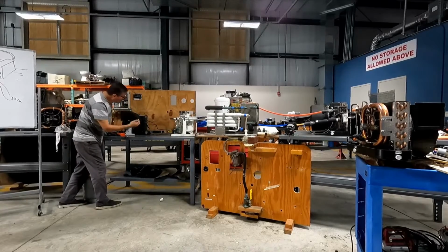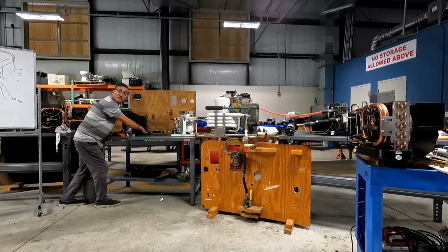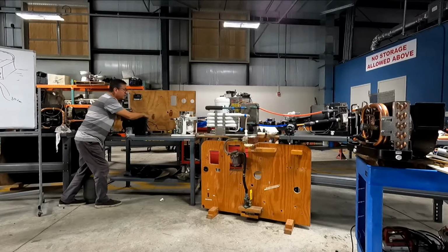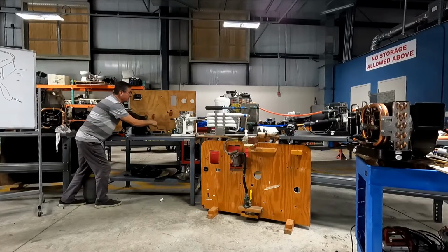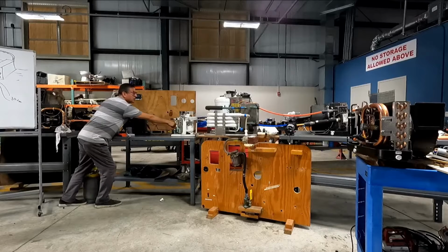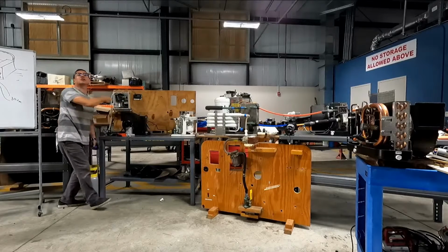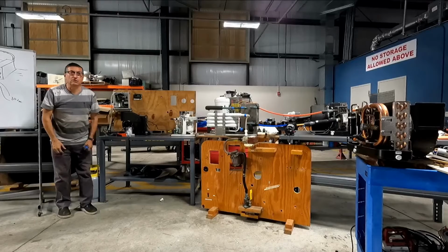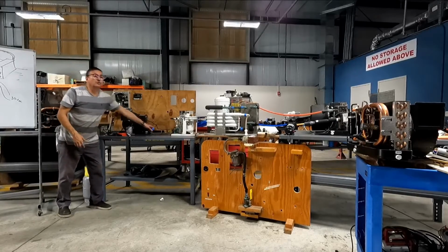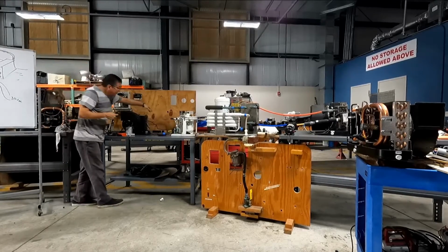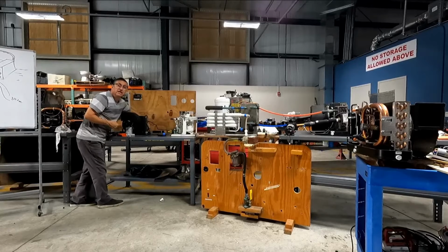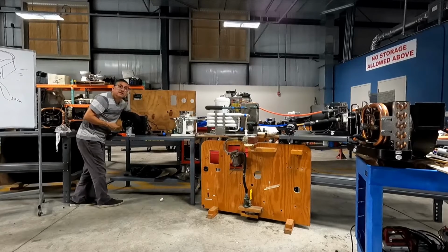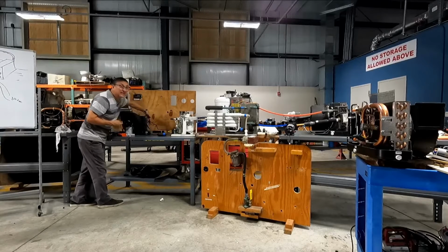Low pressure and low temperature, it enters the bottom of the evaporator and starts the process of evaporation of the refrigerant. The refrigerant goes out here fully evaporated and returns to the compressor, and the cycle continues. This is the refrigeration cycle. Yes or no? Yes. Pay attention. When the refrigerant enters the bottom here, how are the pipes? Cold, frozen. The pipes here are practically frozen.